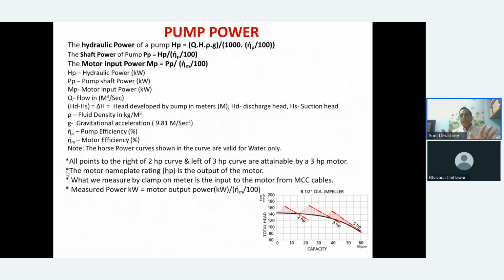Now let's come to it: we know all the head requirement, and we know the flow requirement already through the heat and mass balance and the process, that is what we need. So we have arrived at the hydraulic power now. Hydraulic power is Q H rho g divided by 1000. For pump power, you divide this hydraulic power by the pump efficiency, and the motor input is this pump power divided by the motor efficiency. So you arrive at the motor input power. This is a very simple formula that you can use. And as we have said, in all the curves here, for a particular 8.5 diameter impeller, the curve is here, the pump performance curve, and these are the HP lines. So 3 HP to 2 HP is all 3 HP, and 5 HP to 3 HP is all 5 HP. You have to take the higher one and arrive at this.